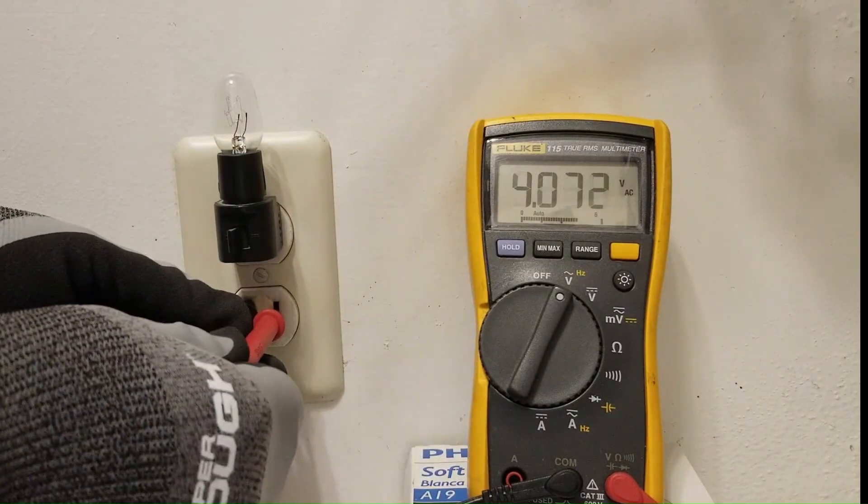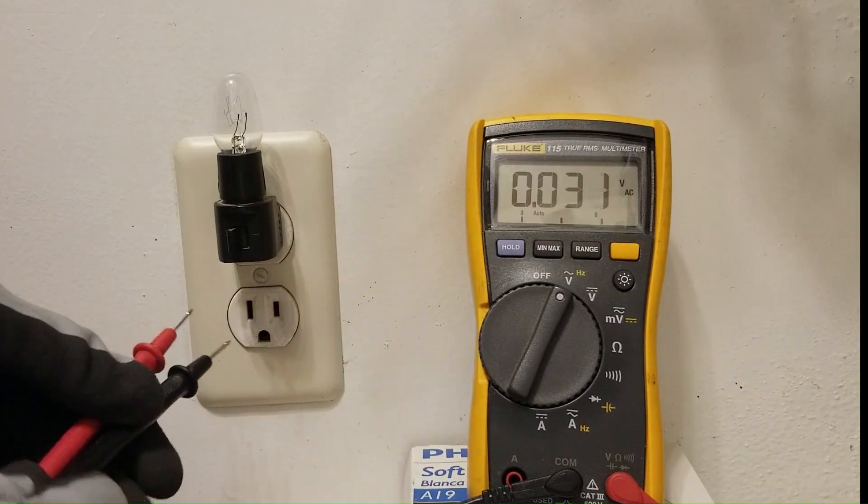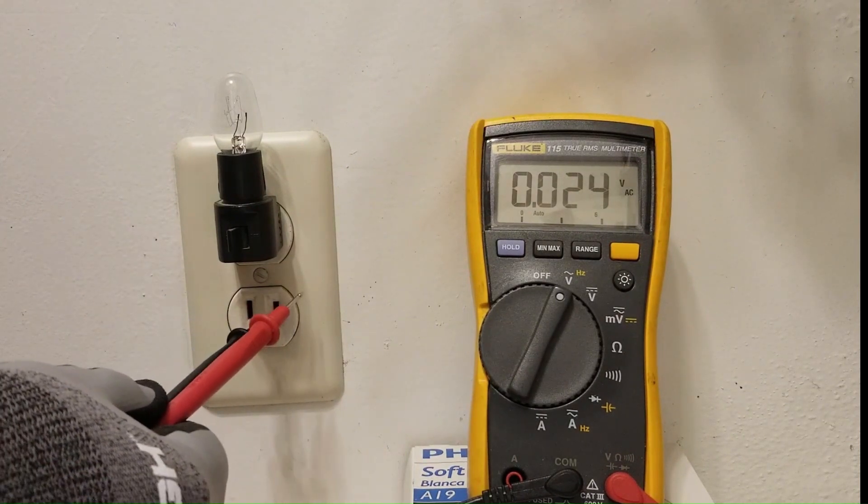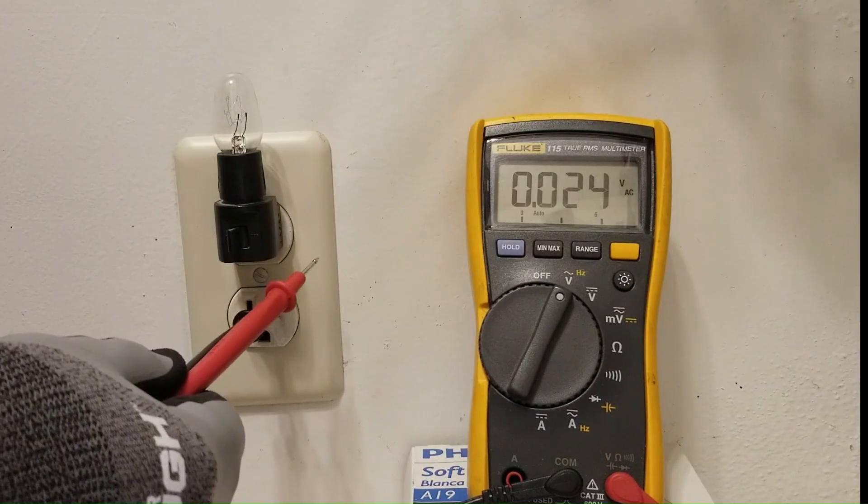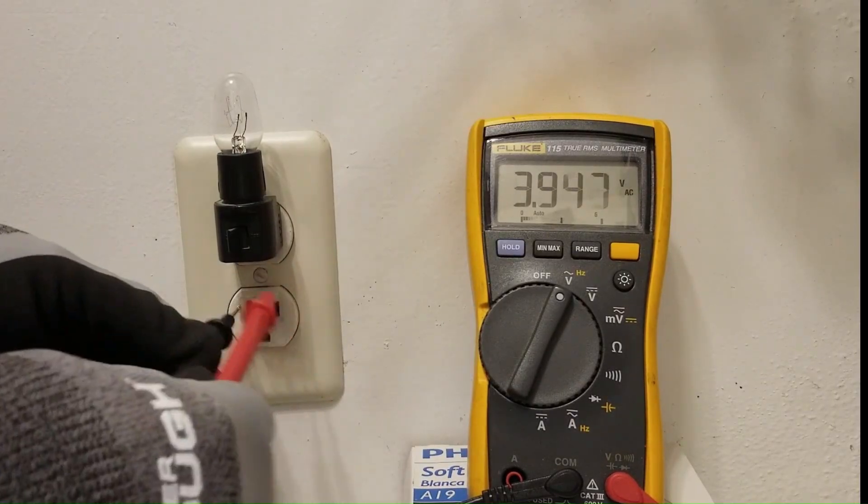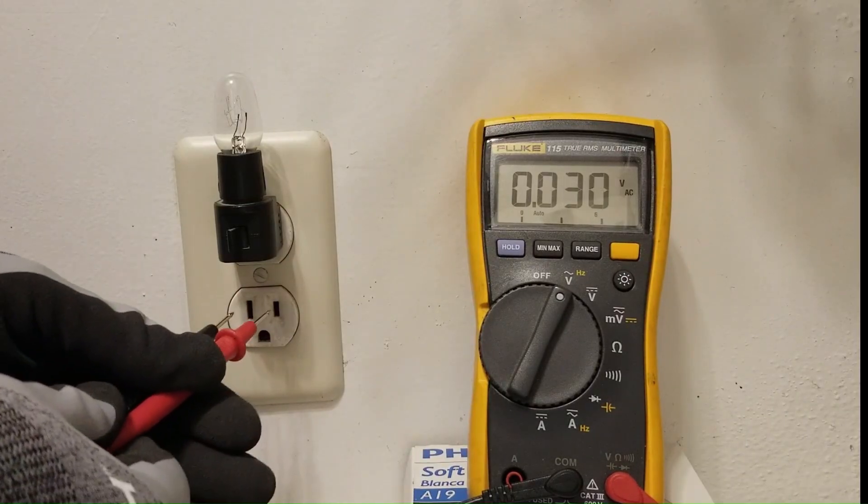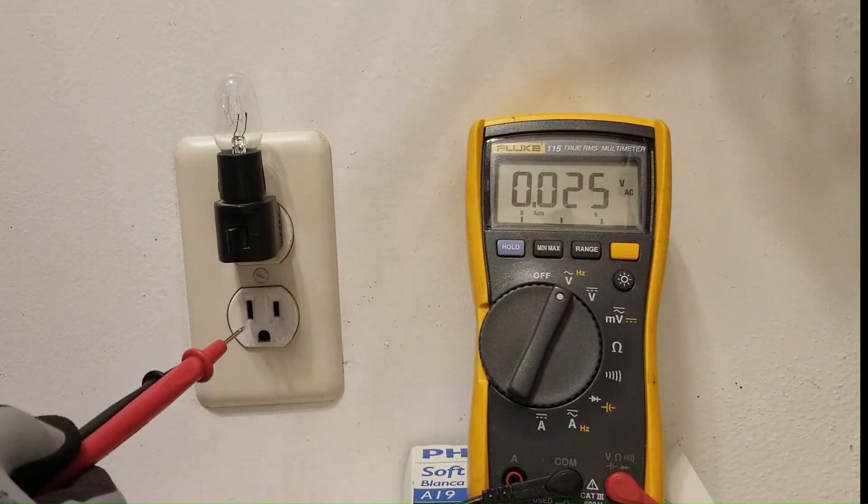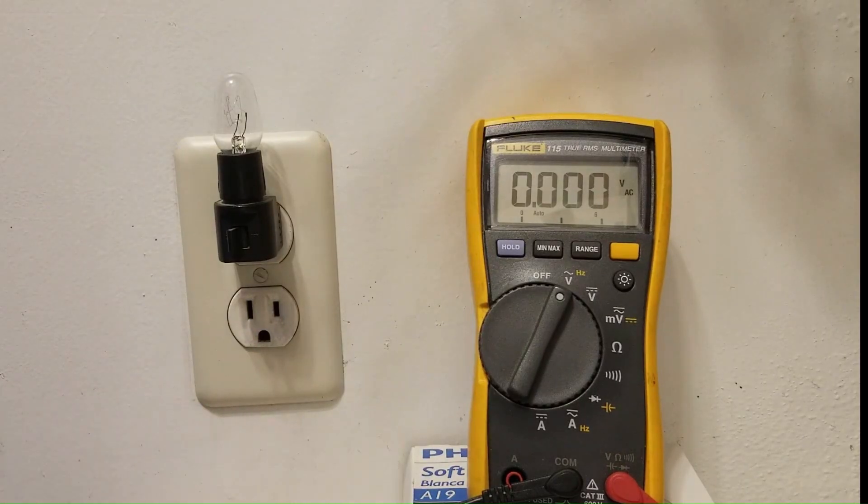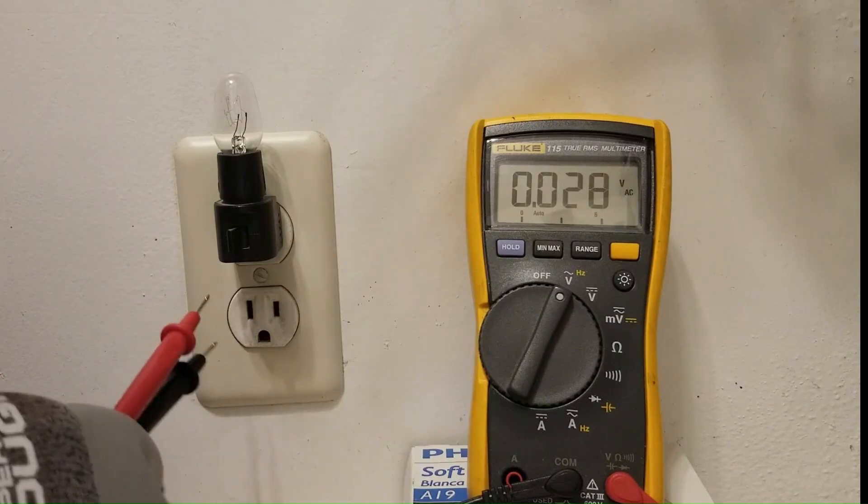So if we have a floating neutral or loose neutral, that neutral is going to go up to the level of hot because if hot is okay, it's going to stay at 120 volts. And if the difference between hot and neutral is only four volts, then that would mean that neutral is at somewhere around 116 volts. Neutral should always be at zero volts, very close to zero volts, give or take a few tenths of a volt.